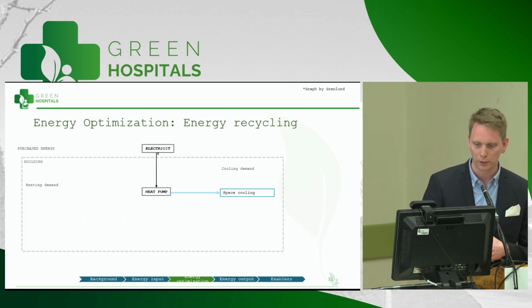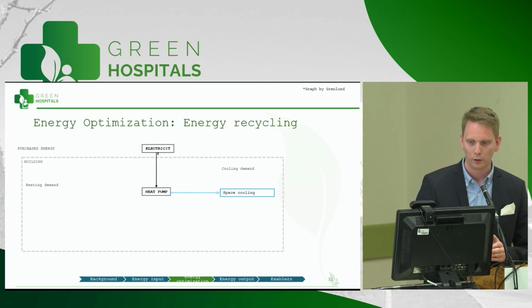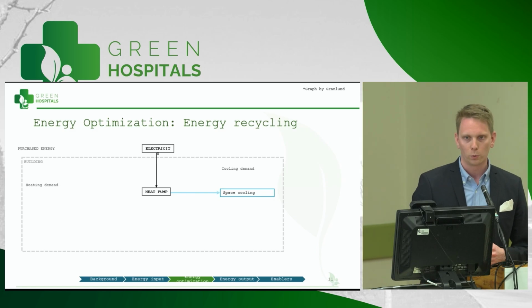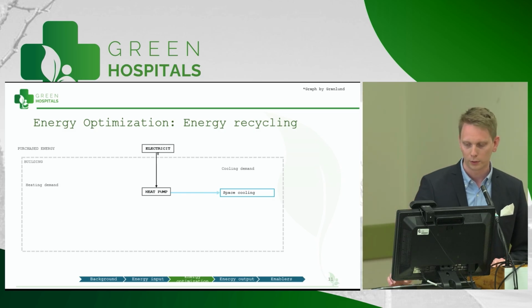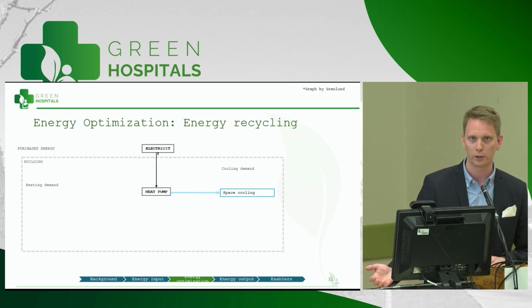Then if we jump inside the hospital, we have created an energy recycling system, and in the middle there is the heat pump, which is responsible for the space cooling. So whenever a room is too hot, the heat pump pumps the heat out of it, and we can use this heat. Typically this heat is pumped outside of the building.